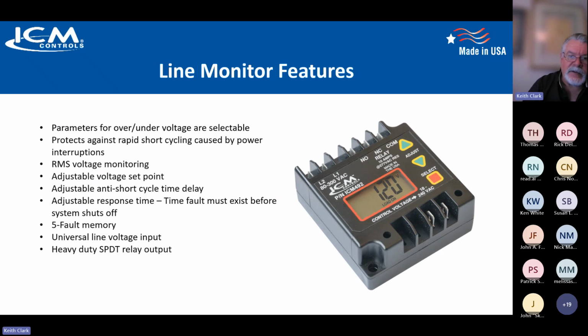It protects against rapid short cycling caused by power interruptions. True RMS voltage monitoring. That means it's like putting your meter on there. You've got your Fieldpiece meter on there. It's reading the same way that would read. Adjustable voltage set point. You can calibrate it for that incoming voltage so that you can set your over and under parameters, and then adjustable response time. How long are you going to let it interrogate before it actually shuts the system off? And it's got a 5-fault memory, which is really handy because then you can see if you're having a continued condition. Man, I've got the last 5 faults are all brownout, and that's going to do damage to my equipment. Well, now you might be able to talk to the power company and say, hey, we've got a situation out here. Universal line voltage input.